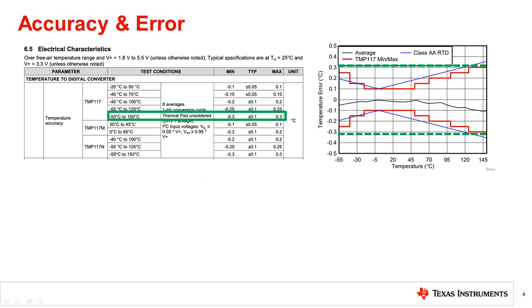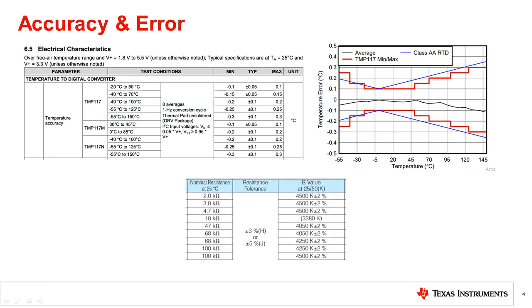Analog sensors like NTC thermistors specify the accuracy in terms of the resistance and beta value tolerance. These are often specified as a percentage and require conversion to absolute scale. Additionally, the nonlinear behavior may lead to absolute error much larger in a specific temperature range. Although not all systems require such a high degree of accuracy or linearity, it is important to understand the specifications and how additional error may still affect the overall temperature measurement.